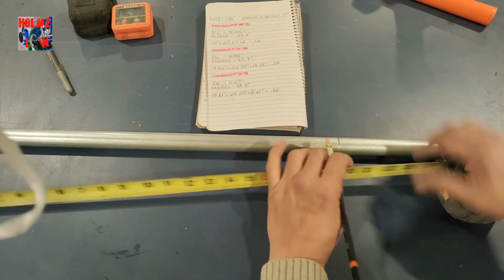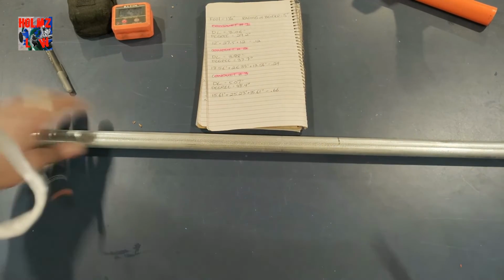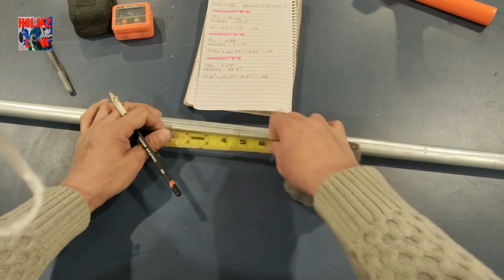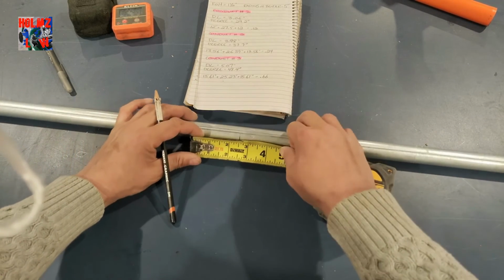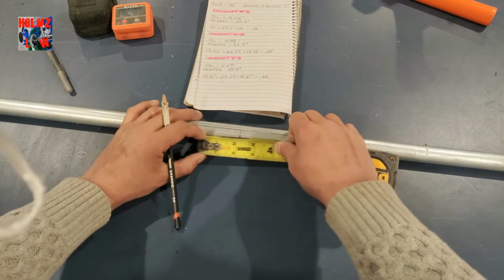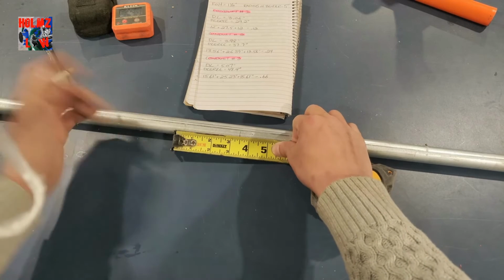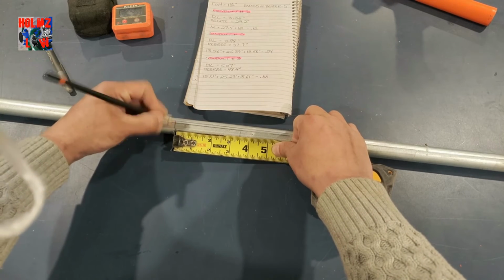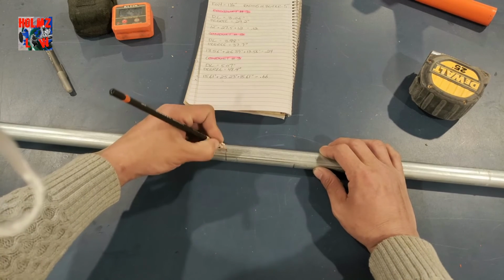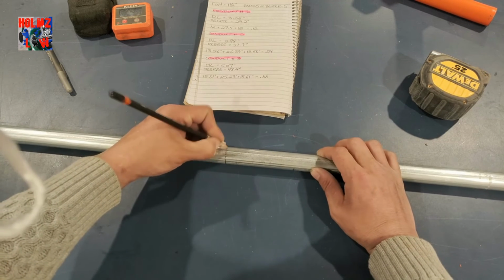26 3/8. Okay, now, same thing goes. Nothing changed. The developed length, we're going to divide that in two and split it on either side of the center. That's what we do. So we have the 2 plus the front of hook measurement gives us 3.5 inches.